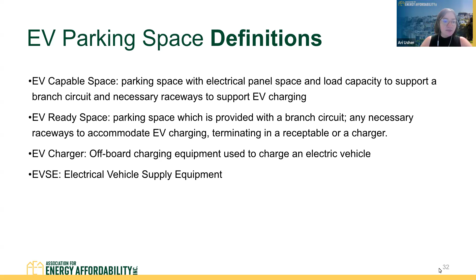Under 2022 CalGreen, there are EV infrastructure requirements, for both new construction and alterations. For new construction, all multifamily buildings will need 10% of total spaces to be EV capable, meaning they have electrical capacity. Then 20% of total spaces need to be EV ready, meaning the branch circuit is installed and there is a receptacle ready for an EV charger to be plugged into it. Additionally, multifamily buildings with more than 20 dwelling units need to have 5% of total spaces with an EV charger installed.